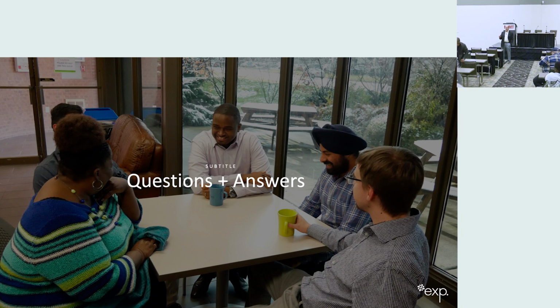There's really no low-hanging fruit, but I would definitely look at your KPIs and see where you can make the most difference. One is metering, if you get your meters and you're not within your benchmark, you can immediately bring that down. Fault diagnostics is really good too, looking at things you already know in your building. If you have simultaneous heating and cooling, that's a problem. If you see a 2x4 stuck in your outside air dampers, or your mixed air plenum doors open because they don't want to freeze the coil, those are indications you're doing something that's probably not right, and you need to increase your performance.